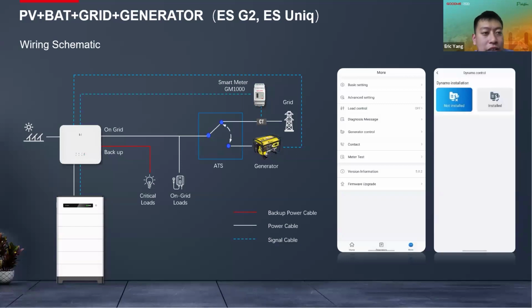And this is the PV and battery, also grid and generator solution. It means in some countries, the PV and battery system will work together with the generator, because in some countries the customer has a generator, so they want the generator to charge the battery. Also, if they have PV and battery, the generator does not work. If there is not enough PV and not enough battery power, the generator will support the loads.